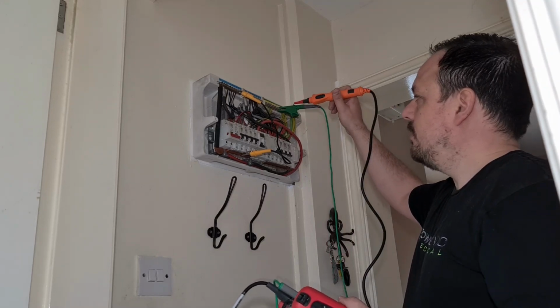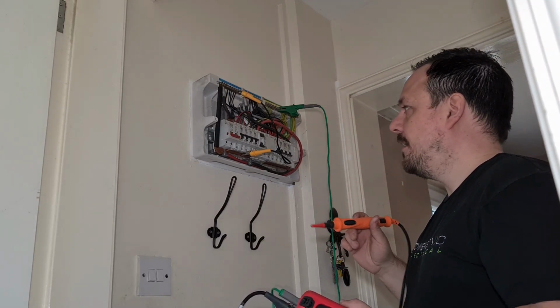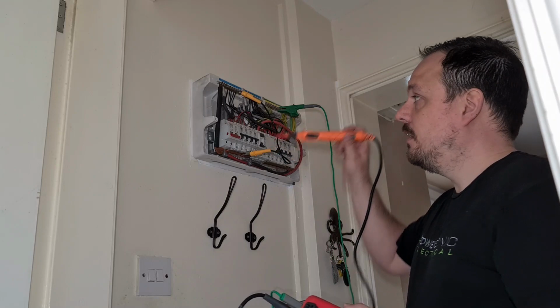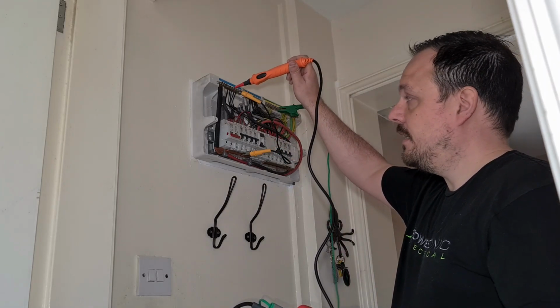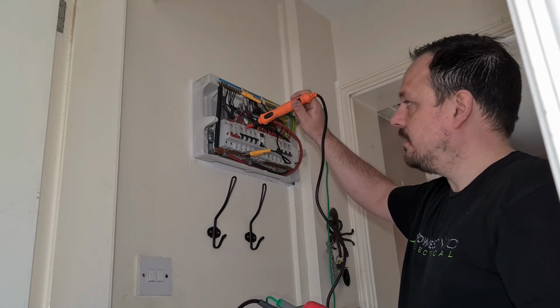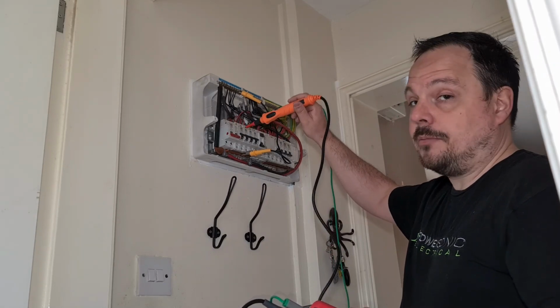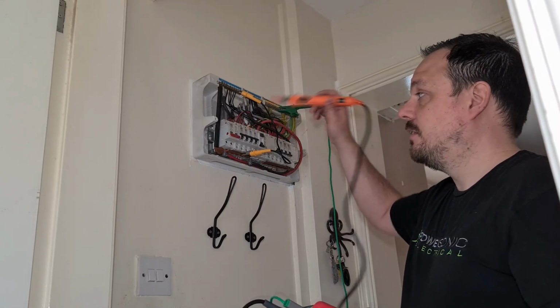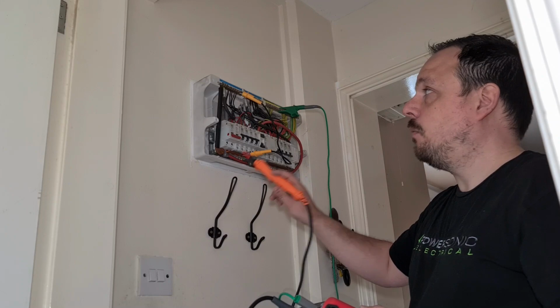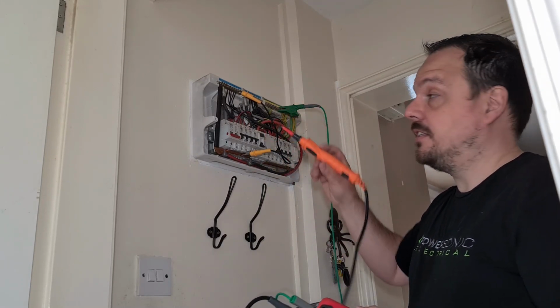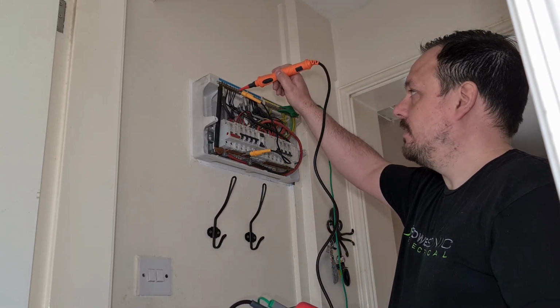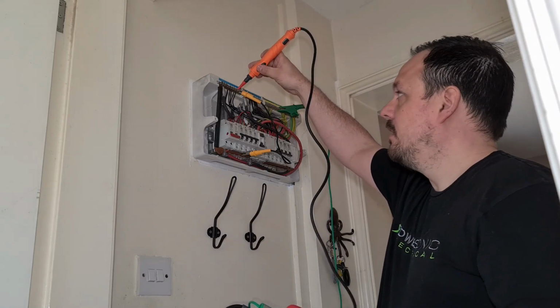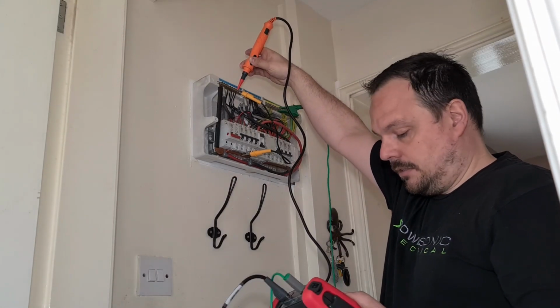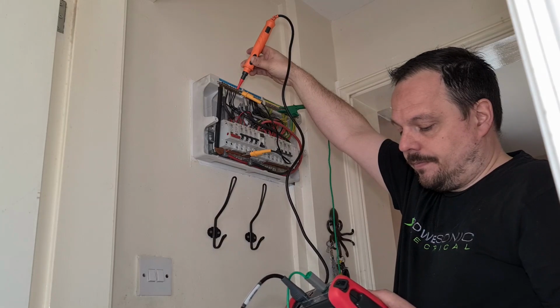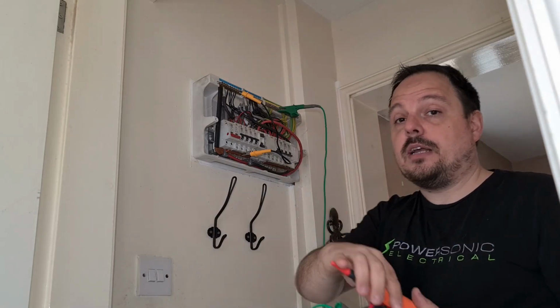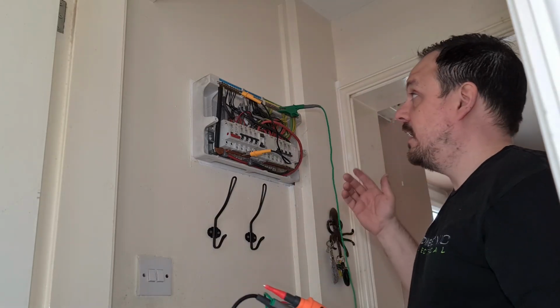I've got the crocodile clip up onto the earth bar there, and using my probe now, I could go onto this neutral bar to take the measurement, or into the little cage terminal on the lines, or onto the bus bar. Anywhere I want gives me a connection to take the measurement. So I'll stick it on these top screws up here, hit the button, and there we go.